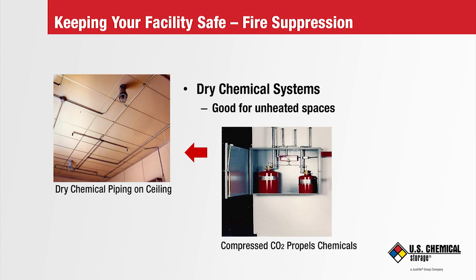Now there's dry chemical systems. A dry chemical fire suppression system, instead of a water-based system, has fire extinguishing powdered chemicals with added particulate material to provide resistance to packing, moisture absorption, and caking in the piping to achieve a proper flow. It extinguishes the fire by smothering and interfering with the combustion process.